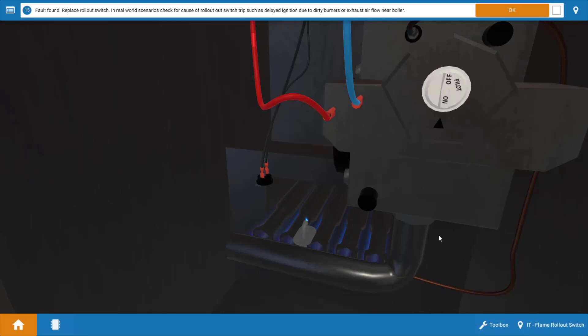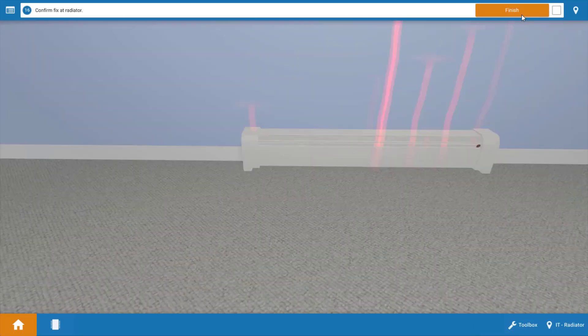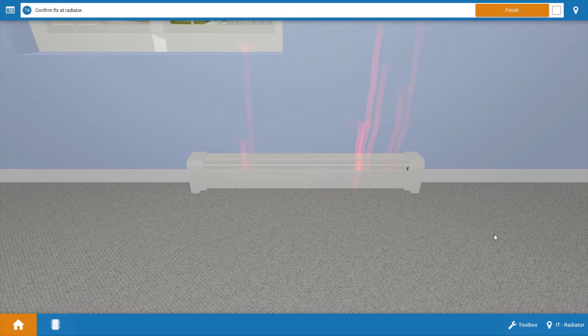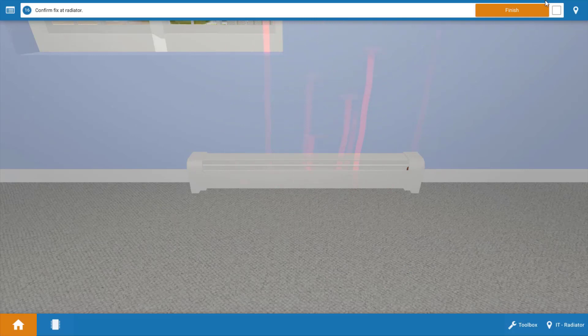So you should verify one full sequence of operations to make sure things are working okay, and also go up in the house and make sure that heat is being delivered to the space. And we can see by this baseboard radiation, this red graphic, that in fact heat is being delivered to the space.